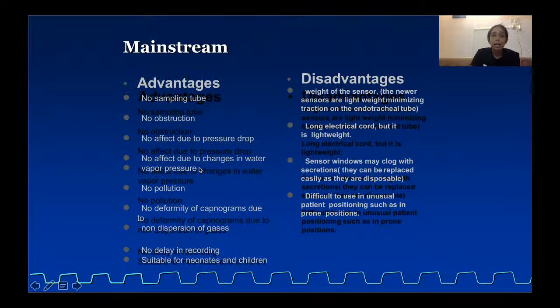There is no loss of gases, because in the side stream, if there is a small leak here, there can be release of gases. Over here there is no loss of gases. However, this is heavy. What is the problem with this is it is bulky, the weight, right? Because of the bulky nature, it cannot be used in prone positions. It can cause disconnections. The entire tube hangs, so it can cause kinking of the endotracheal tube, increase in airway pressure, and can be quite disastrous.